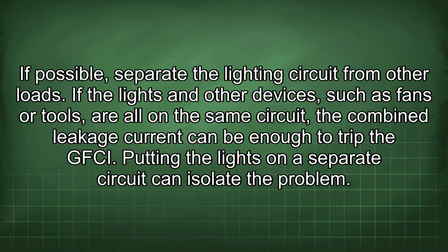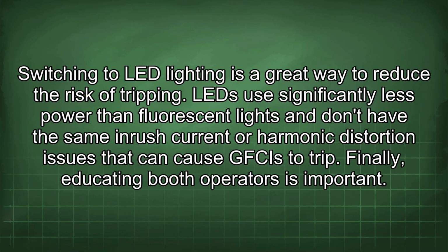If possible, separate the lighting circuit from other loads. If the lights and other devices, such as fans or tools, are all on the same circuit, the combined leakage current can be enough to trip the GFCI. Putting the lights on a separate circuit can isolate the problem. Switching to LED lighting is a great way to reduce the risk of tripping. LED use significantly less power than fluorescent lights and don't have the same inrush current or harmonic distortion issues that can cause GFCIs to trip.